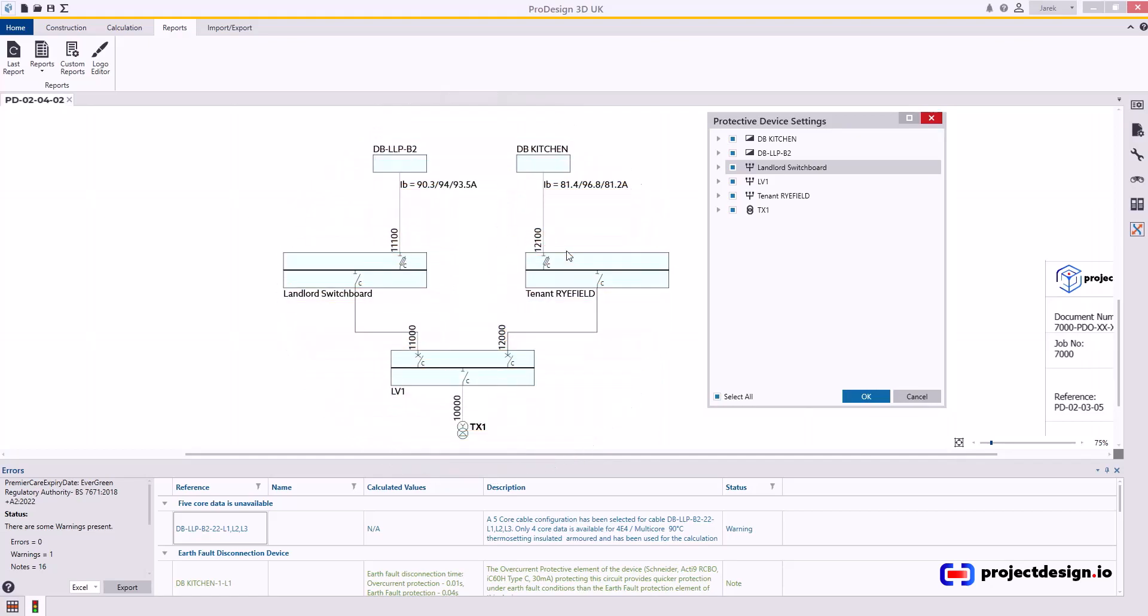Before you go, it's pointless to create this report for all the devices in your electrical system because you will have RCDs, RCBOs, MCBs, fuses. Those devices do not have settings you can change, so it's pointless to include them. This is only useful for ACBs and MCCBs.